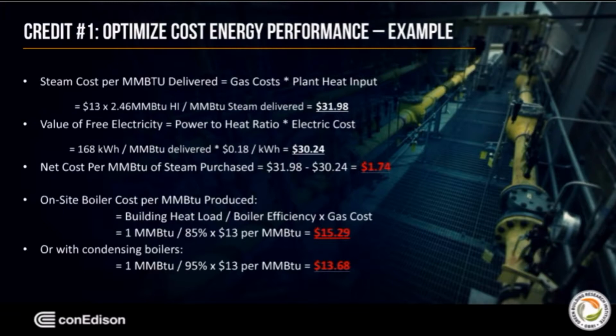It's pretty good. Let's now look at the case of an on-site boiler in which the cost per million BTU produced equals the building load divided by the boiler efficiency times the gas cost, which is 1 million BTU divided by the 85% efficiency times $13, which adds up to $15.29. This is about 90% cost improvement. And even if the boiler were 95% efficient, then the on-site boiler cost per million BTU produced would be $13.68. So steam would still be the better option.